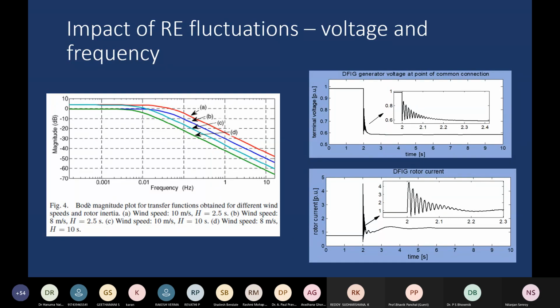So inertia H equal to 2.5 seconds means that it takes 2.5 seconds to accelerate that particular shaft from zero speed to its synchronous speed. So inertia of 10 seconds means that it is a very heavy shaft, and inertia of 2.5 seconds means it's a very light shaft. So at low wind speed and at low inertia, you can see that the cutoff frequency is higher because the shaft inertia is very low. But if the shaft inertia is very high, the cutoff frequency is lower.